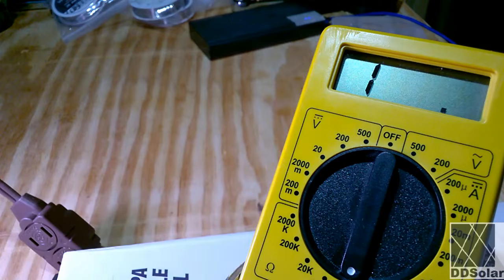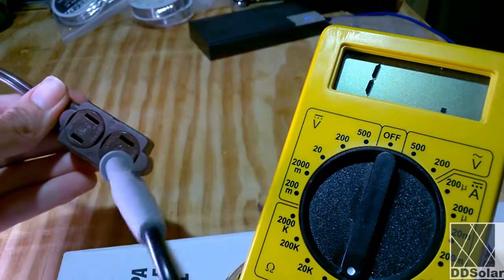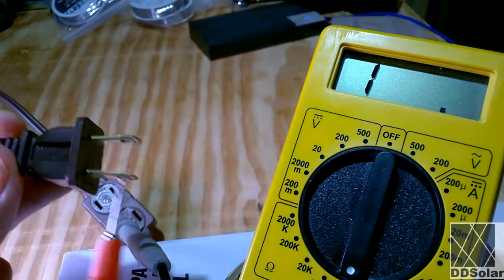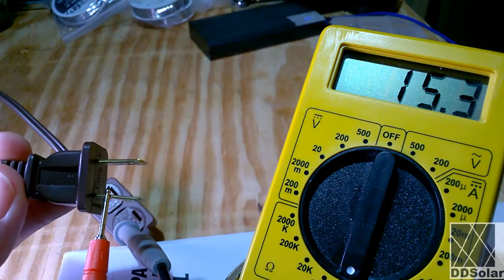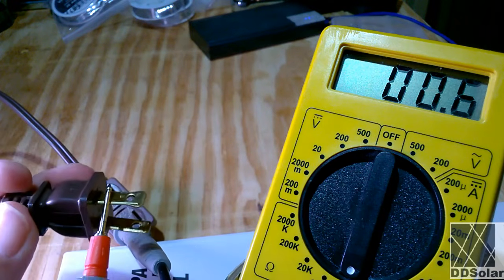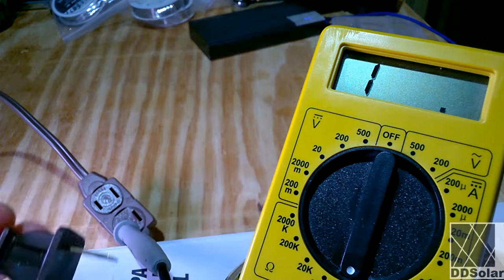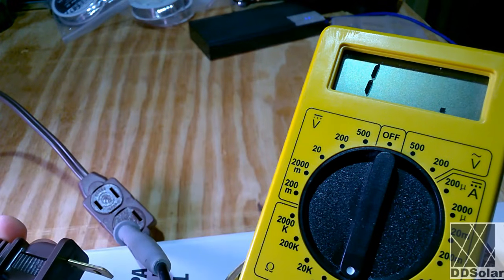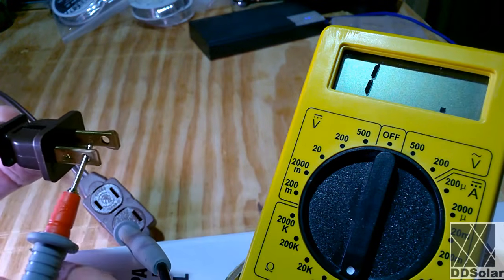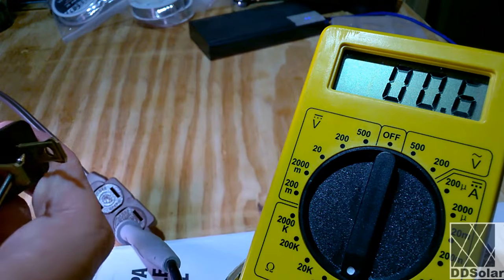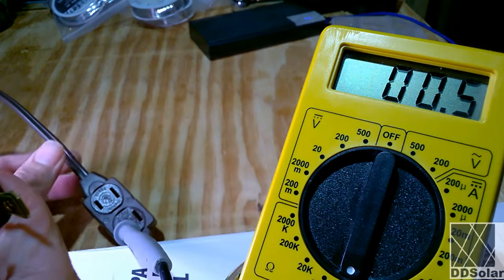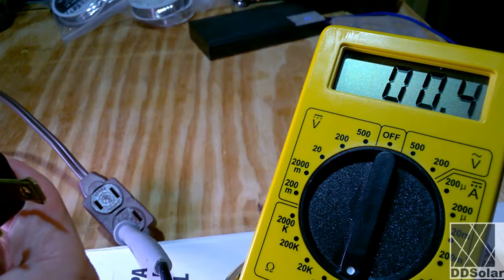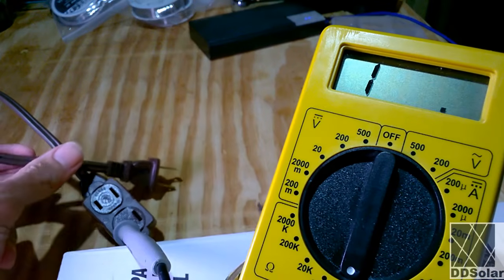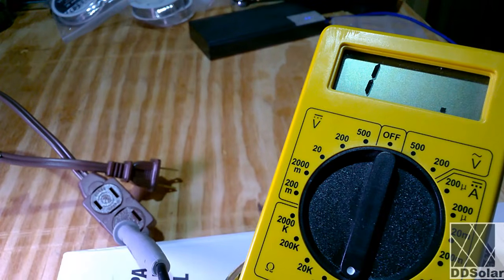Now, what if I stuck my meter probe in one side like this, and I got nothing? So every time I touch this, the meter says there's nothing there. It just doesn't do anything. A lot of times that means the cord itself is bad and you have a broken wire. Another trick you can use is simply attach the probe, get a good connection, and then start moving the cable around. Move the wire around and see if the reading changes. If it starts turning on and off, you know you have a frayed or broken wire inside the cord and you need to dispose of it.